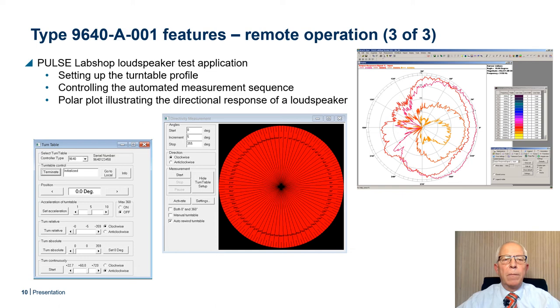Finally, on the remote operation of the turntable — this example illustrates how an existing application made for the legacy turntable has been adopted to support the new high-precision turntable. Only a few changes were made to the user interface, and other changes had to do with the differences in controlling the legacy turntable over IEEE 488 versus controlling the new turntable over USB.